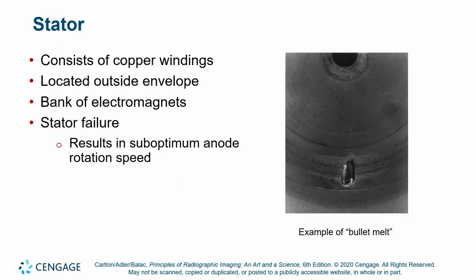Okay, moving on to our stator. Our stator is basically a series of electromagnets arranged like a clock face, such that if there are 6 electromagnets, which is a typical configuration, opposite electromagnets will create a north-south pole. And then as we cycle the power through the different pairs, we create a rotating magnetic field. Okay? The stator for the X-ray tube is actually outside of the envelope. It's still inside the tube housing, but it's not part of the X-ray tube itself. Okay?